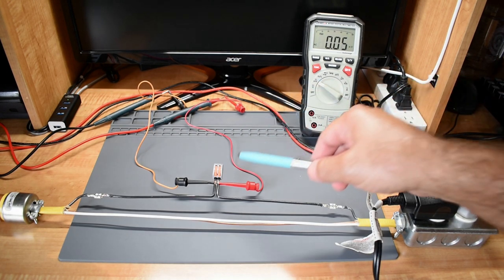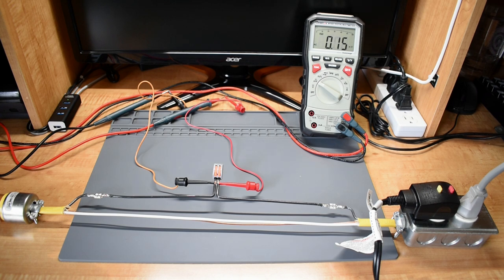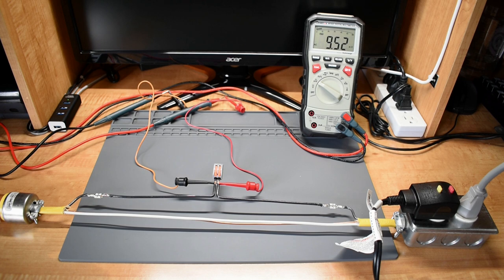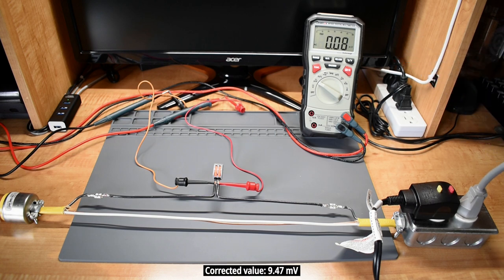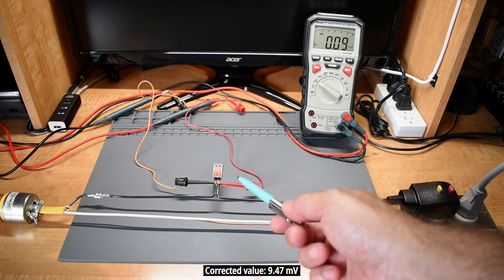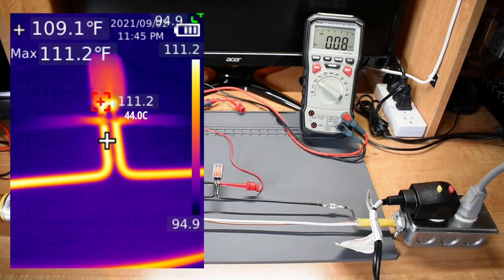Now this connector, right here. And that is it for this connector, fifteen minutes is up. We were right around 9.52 millivolts, and right here you can see the temperature of this connection right at the end of the test.